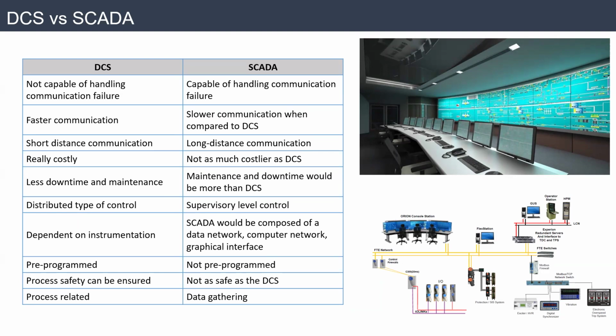SCADA is usually used for third-party systems connected to DCS, or for remote control using RTUs, remote terminal units. This is the main difference between DCS and SCADA. DCS is much bigger and higher in capacity and control than SCADA. For communication speed, DCS is usually much faster than SCADA. And DCS is usually used for short distance, while SCADA is used for long distance.